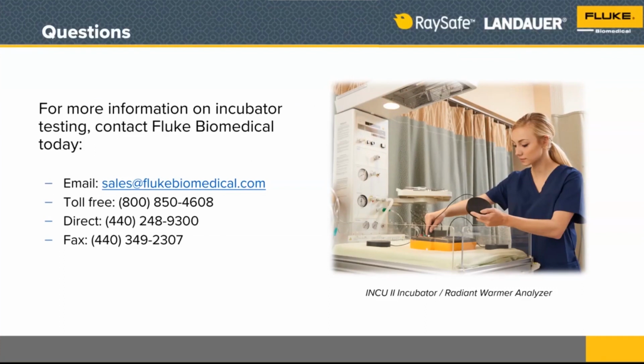Okay, so the first one, Jerry, is around how often should electrical safety checks be performed? So how often electrical safety tests need to be performed depends on where in the world you are. If you're here in the United States, we actually have a local national code which functions as if it was a standard about electrical safety. It's NFPA 99. NFPA meaning National Fire Protection Association.